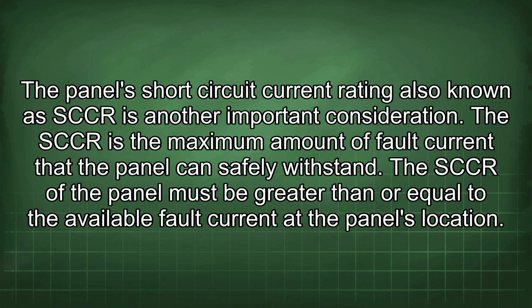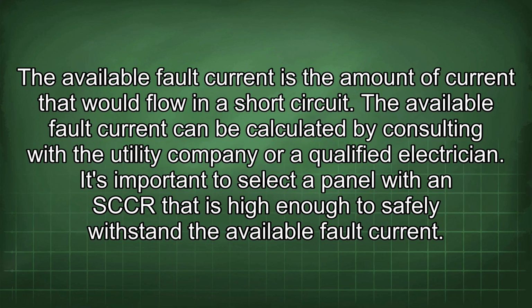The panel short circuit current rating, also known as SCCR, is another important consideration. The SCCR is the maximum amount of fault current that the panel can safely withstand. The SCCR of a panel must be greater than or equal to the available fault current at the panel's location. The available fault current is the amount of current that would flow in a short circuit. The available fault current can be calculated by consulting with the utility company or a qualified electrician. It's important to select a panel with an SCCR that is high enough to safely withstand the available fault current.